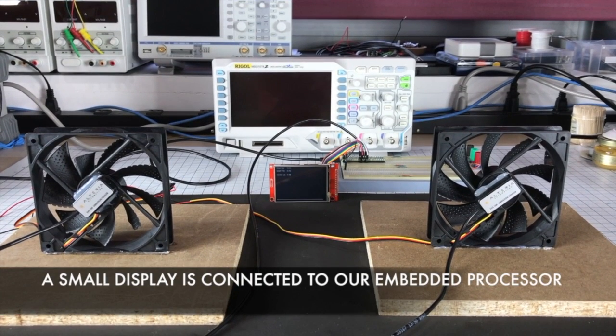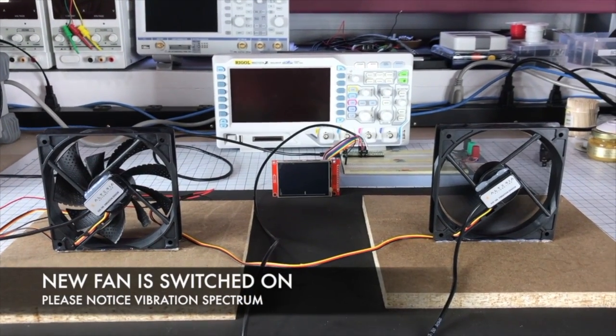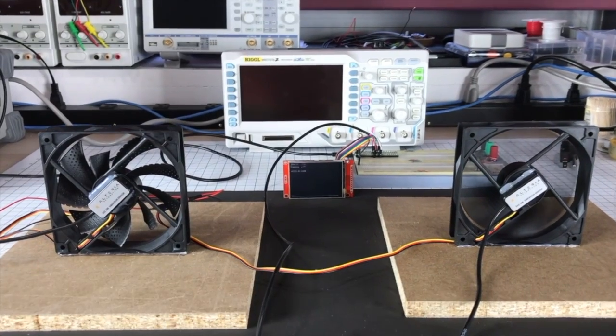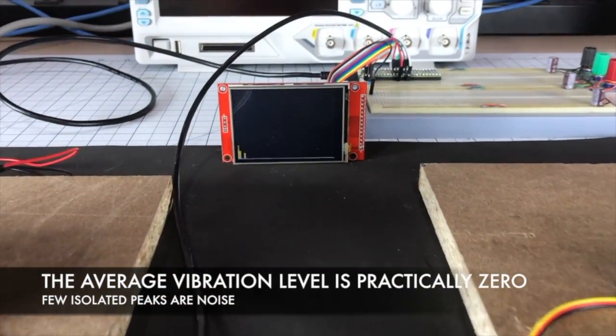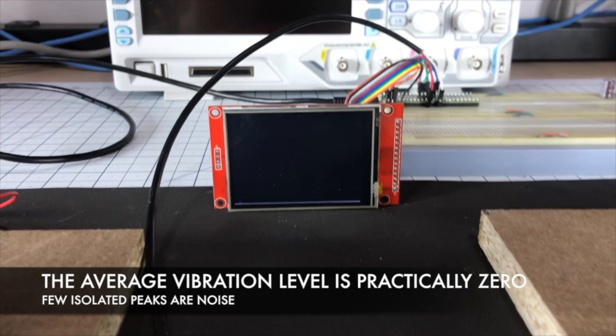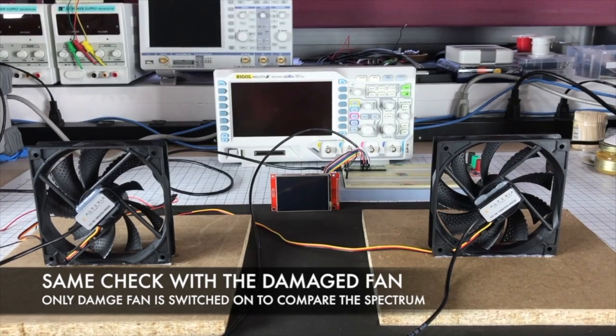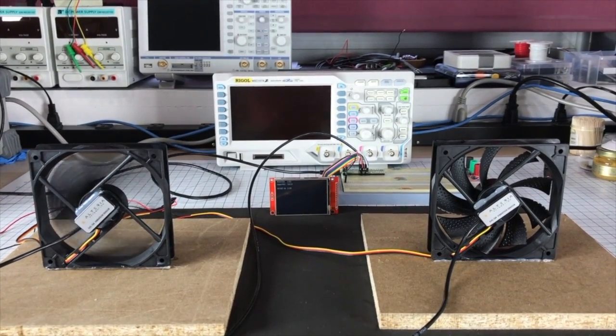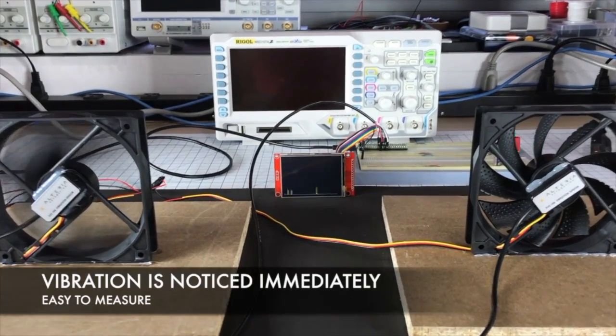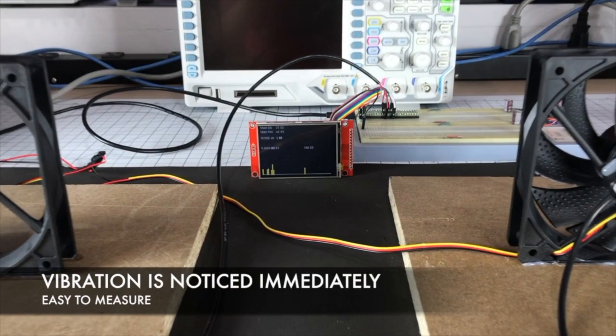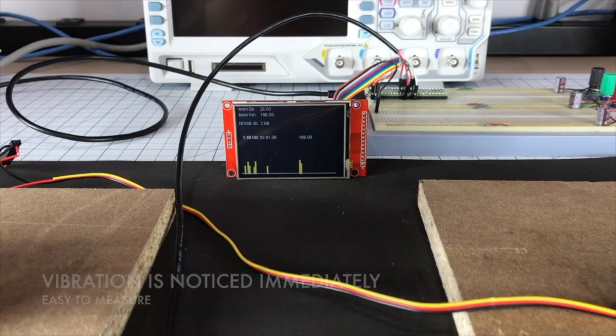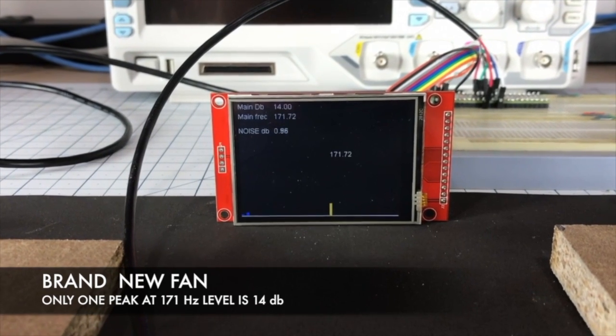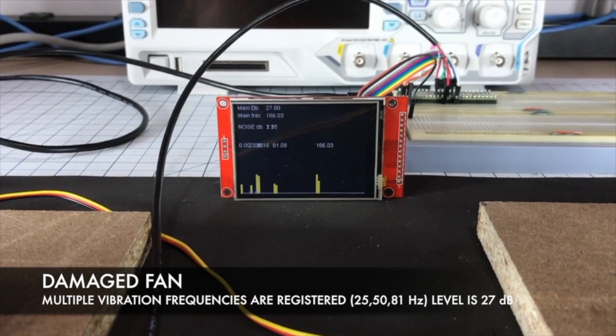Okay, and we are now showing on the small display the frequency analysis preprocessing, and you can see that the average vibration on the undamaged fan is almost none. And now we make the same check with the damaged fan, and you can see that there is a clear indication: certain frequencies are showing up on the display. There is one predominant frequency and some other frequencies on the display that are clearly detecting the imbalance of this fan. So vibration is a measure of the inefficiency of the system.